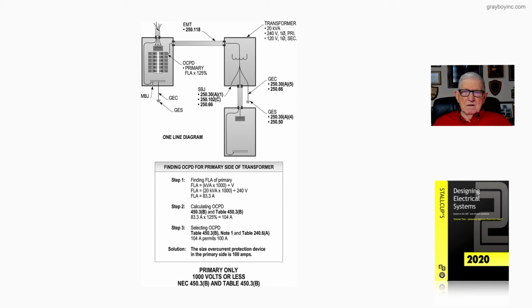Now, the engineer or electrician in Step 3 can apply Table 450.3(B) along with Note 1, select the overcurrent device in accordance with Table 240.6(A), which lists the standard sizes in that table. And notice it was decided in Step 3 to round it down to 100. Usually it would be about 105.6 or something like that before they'd round up usually to 110 or 125 to select the overcurrent device. So it's rounded down here, but you could round up to 110, but that's an unusual size and sometimes will cost you more money than the 100 amp.